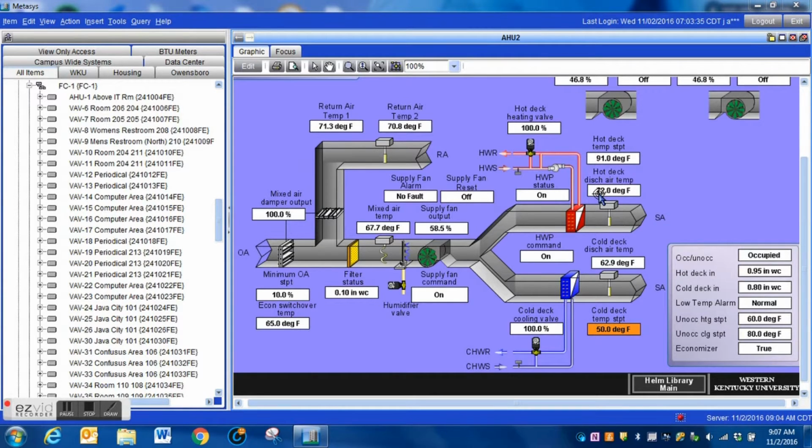You can see in this graphic that it is a dual duct system, and it's just really unnecessary to heat, to waste that energy unnecessarily. The building obviously during the warmer months needs cooling, and heating is not an issue whatsoever.